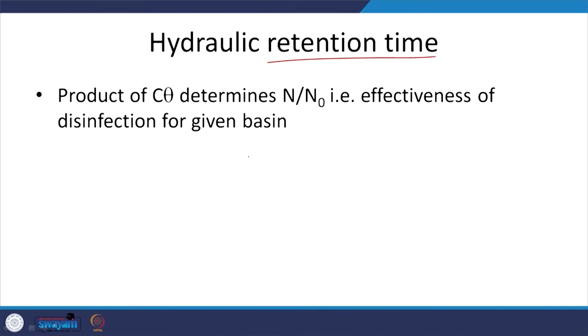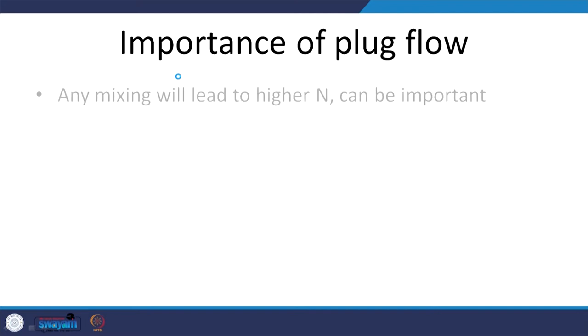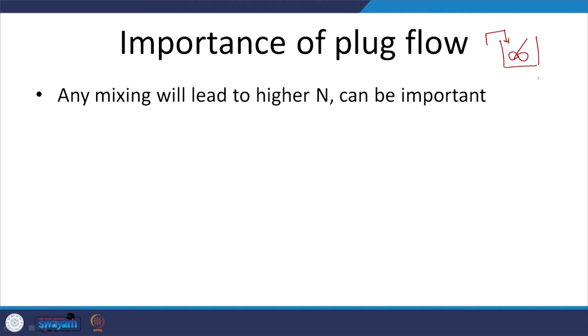The hydraulic retention time θ matters, and the product C·θ — called the dose approach — determines the effectiveness of disinfection. For plug flow versus CSTR: in a CSTR, if water is immediately completely mixed, whatever pathogen-laden water comes in is mixed with effluent, so the effluent cannot truly be zero. That is why we move away from CSTR-type systems and try to achieve plug flow, using long and narrow tanks or baffle tanks.